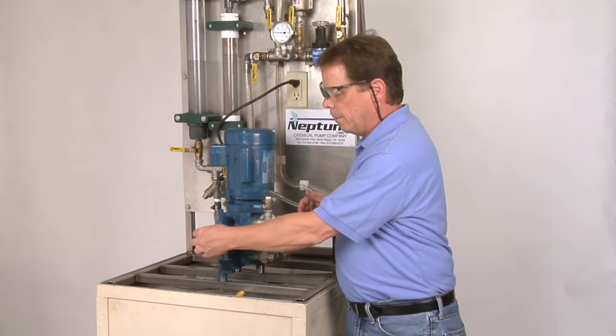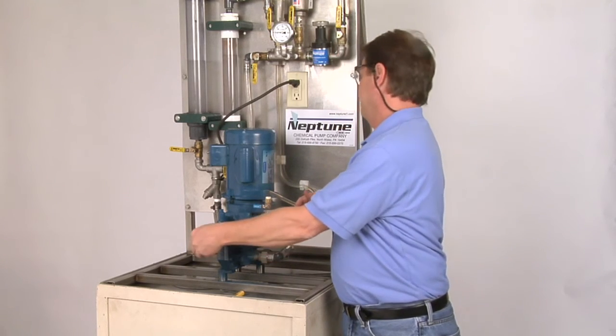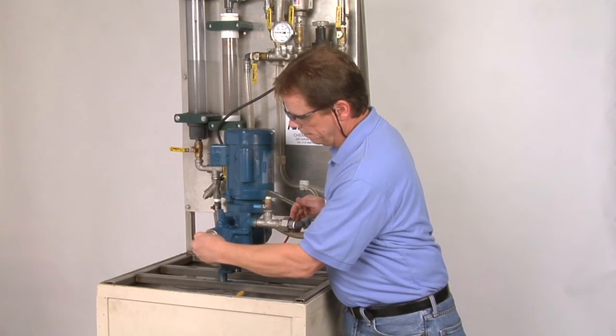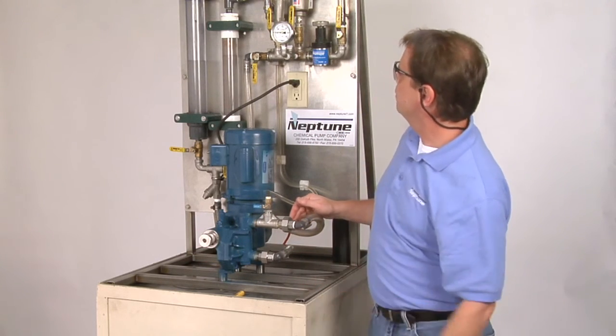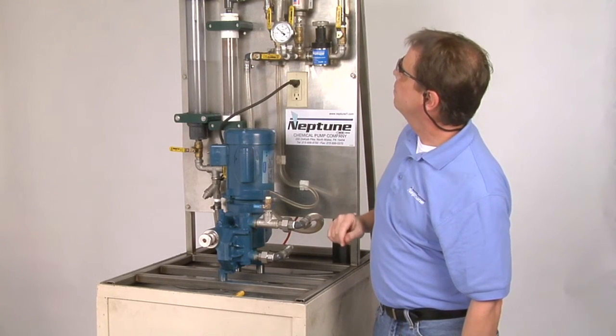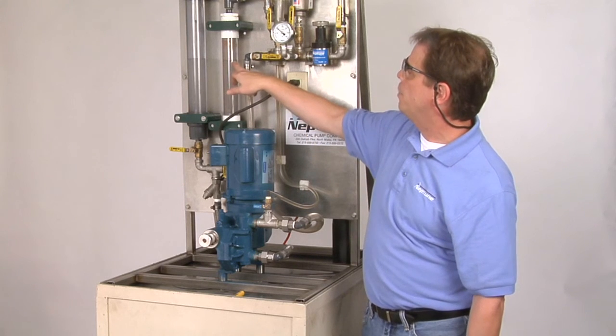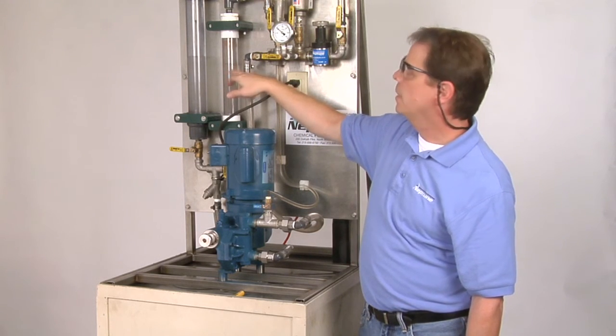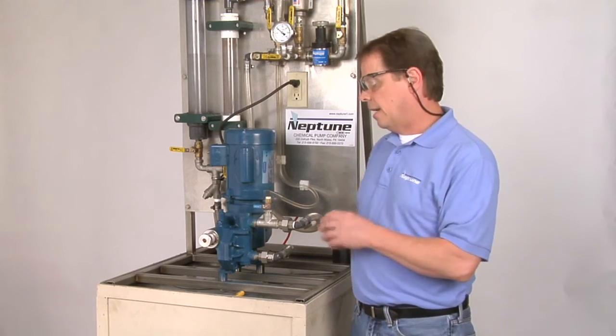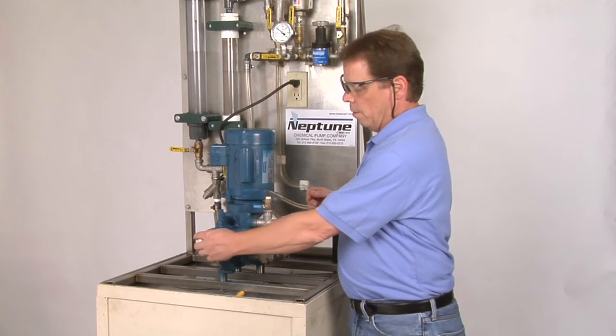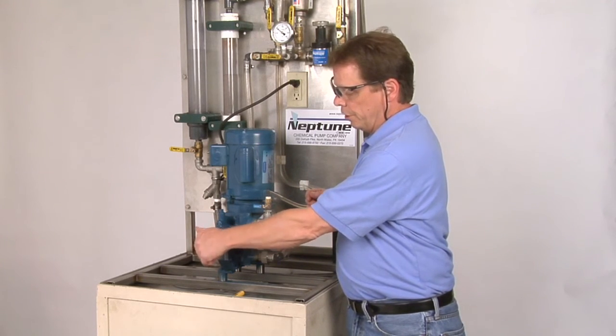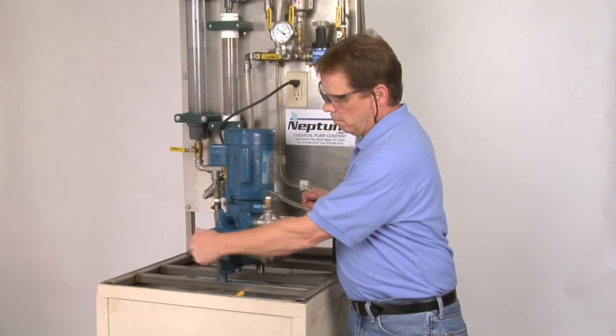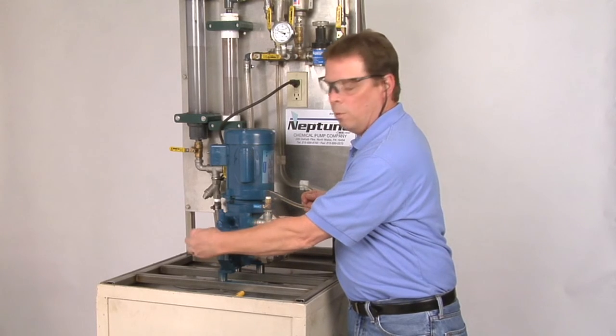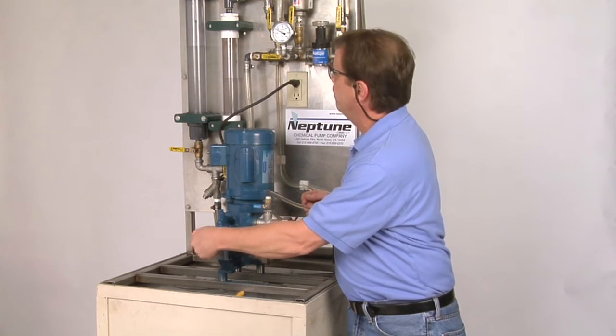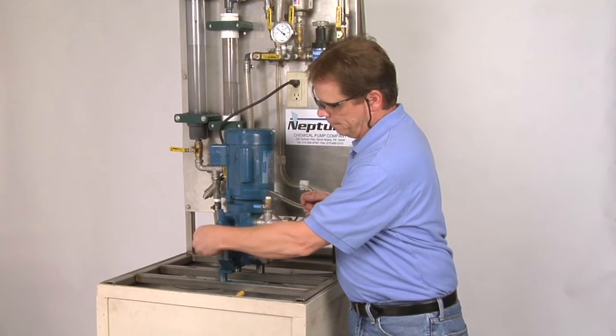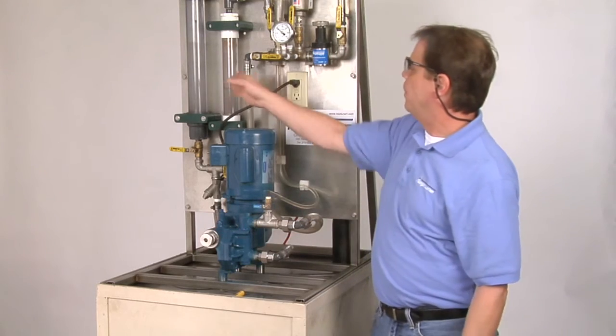And then once we're back at 0, we move it up to 60%. As you can see, we're pumping. And we'll generally let that run for another 5 minutes. Now, again, this pump is ready to go. So, we'll just take it back down to 0. And then we'll run it up to full flow, which is 100%. Now we have full flow.